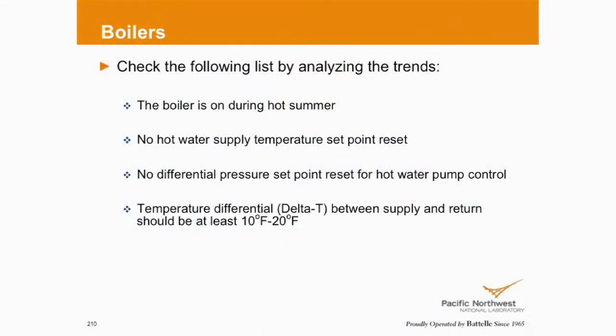How many of you have hot water loops that are not boiler derived but steam derived? So you have a plate and frame heat exchanger or some sort of, okay, are you resetting those loops? Great. Absolutely. Good, okay. On the outside. Okay, great. Differential pressure set point reset. If you've got VFD driven pumps, if you've got a primary secondary, hopefully you're doing some kind of a reset. And then the last bullet there talks about temperature delta.